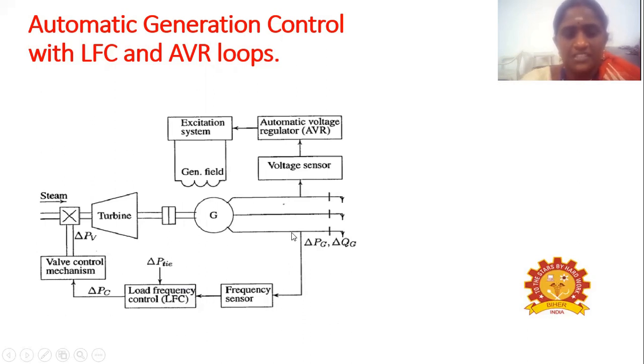First, the output frequency is sensed by the frequency sensor. After that, the frequency is sent to the load frequency control. The LFC checks the frequency of the generator output power against the reference value, and the change in the tie line power. If there is any deviation, it sends a command to the valve control mechanism. If the generated power frequency is much lower than the reference frequency, the valve control mechanism opens and allows more steam to enter the turbine. If you want to reduce the frequency, the valve control mechanism changes its position and only a small amount of steam is allowed into the turbine. Like this, we can maintain the frequency.